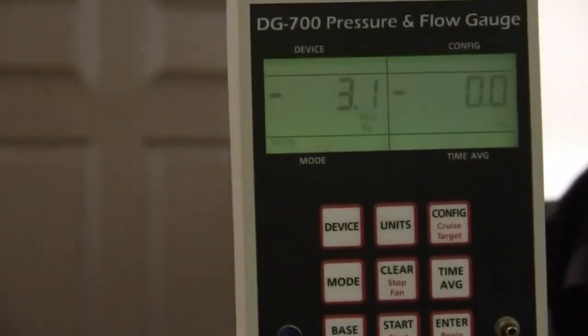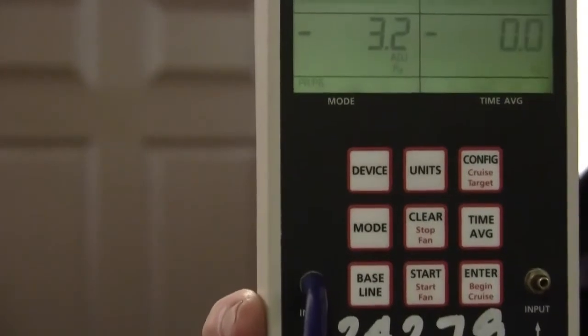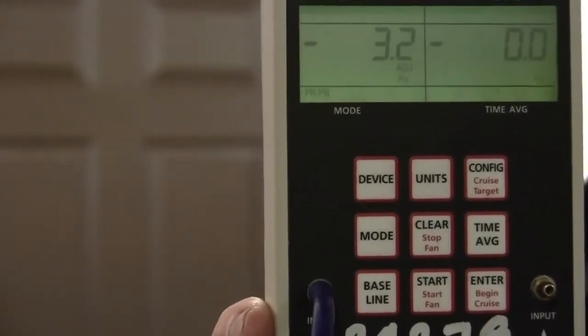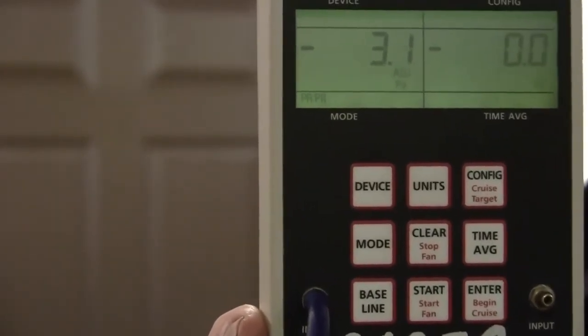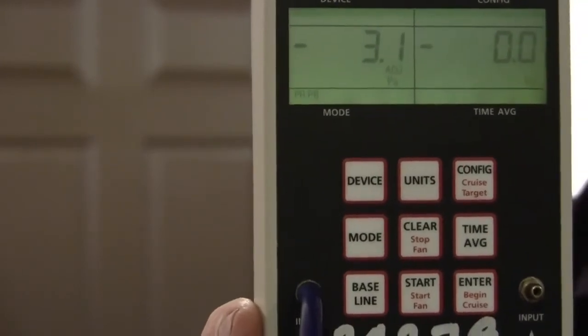Now I'm going to turn on the air handler and check the number again. Okay, the air handler has come on. And I don't know, we're in about the same thing, where little or no effect is caused by the air handler, with the door closed to the combustion appliance zone.